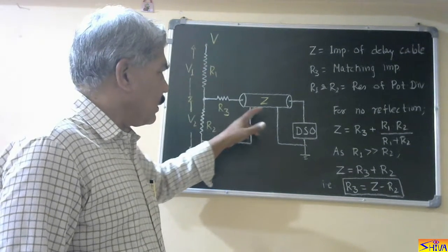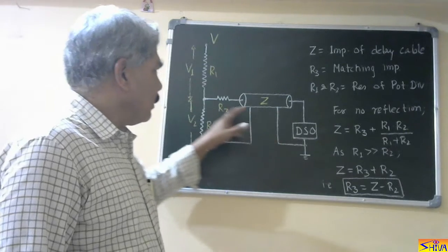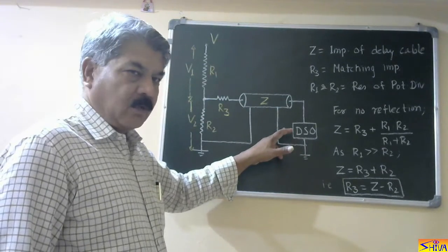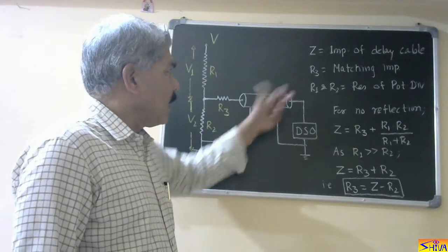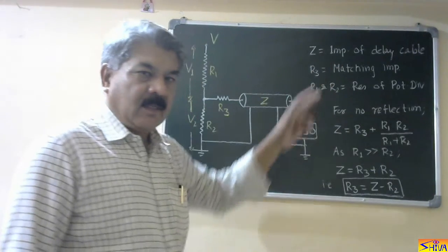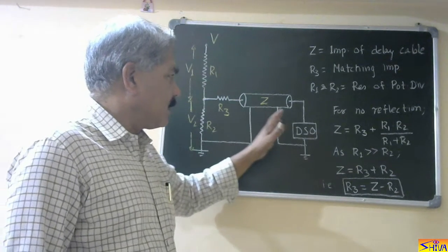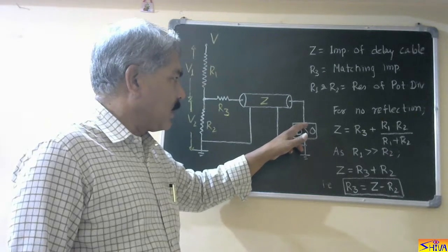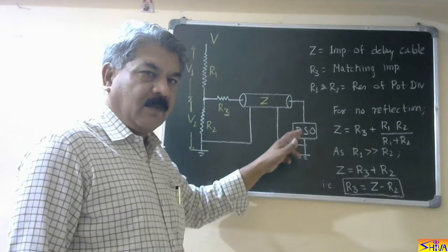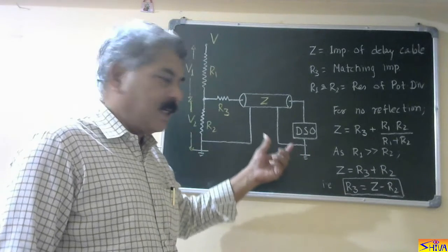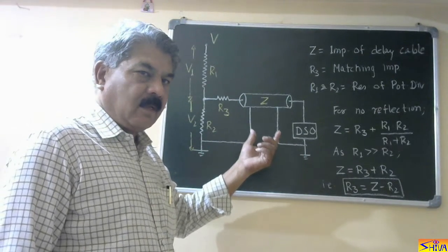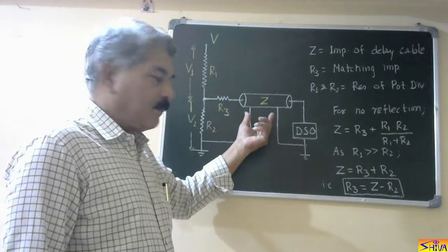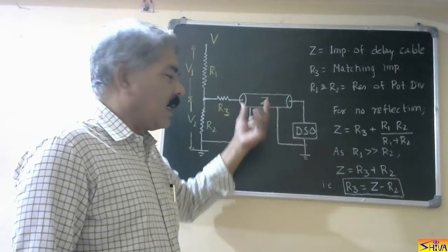So, we have to use a delay cable to take the sample of the voltage from this potential divider up to the digital storage oscilloscope. This delay cable, having impedance Z, serves two purposes. First is, it slightly delays the arrival of this transient over-voltage to the DSO, so that the DSO becomes ready for accepting this voltage. And second, it avoids electromagnetic interference, which may cause distortion in the waveform.